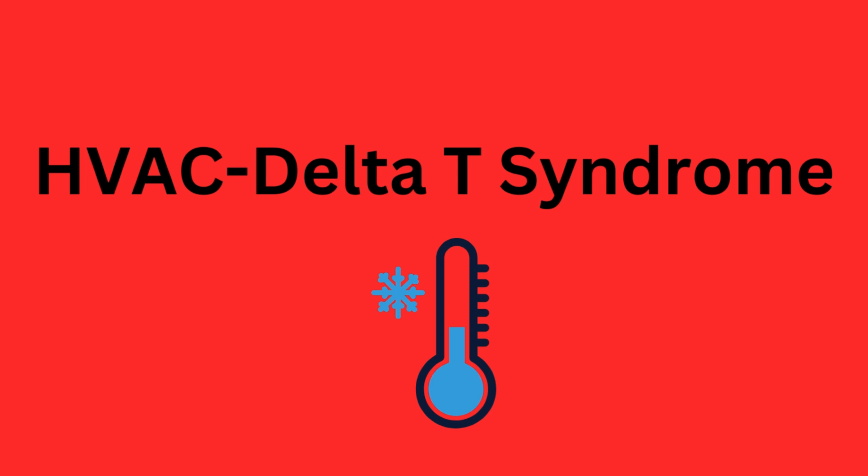Frost on evaporator coil. Ice or frost buildup on the evaporator coil can be a sign of improper delta T. Unusual noise. The system might make unusual sounds due to strain or improper functioning. Poor airflow. Reduced airflow from the vents can indicate an issue with the delta T.